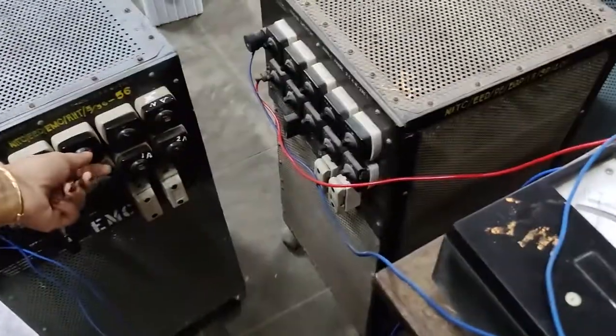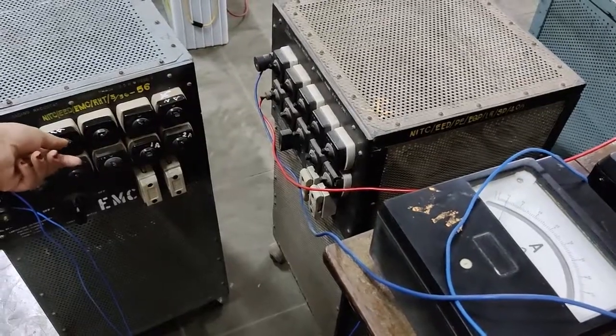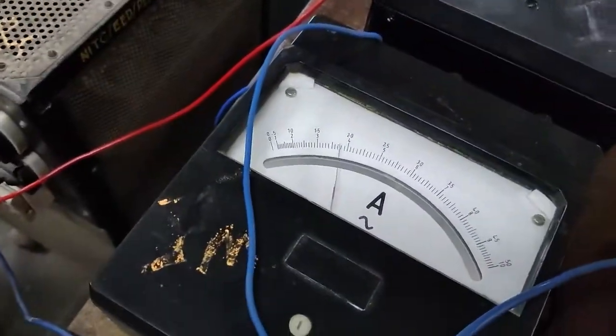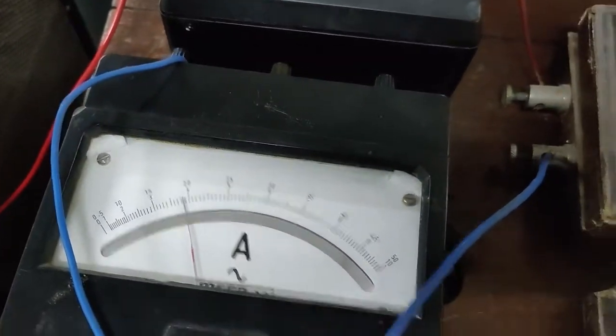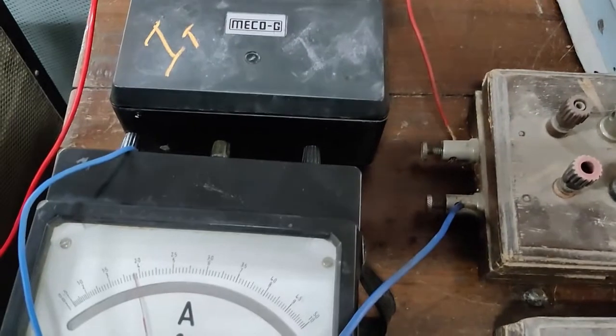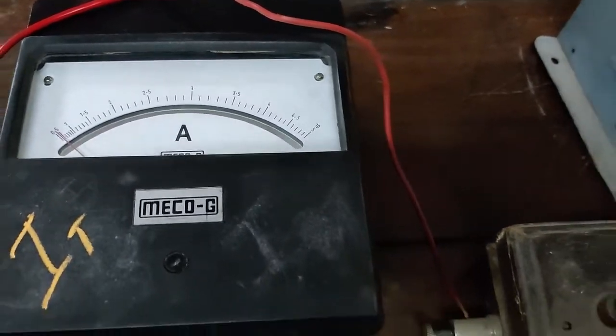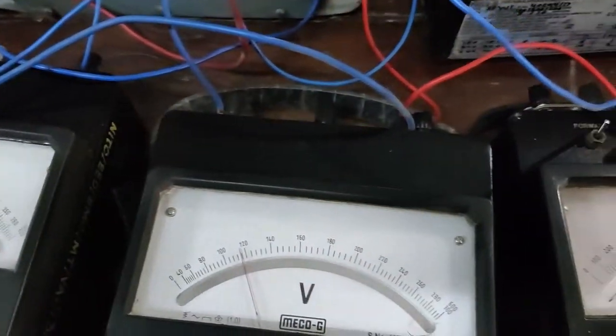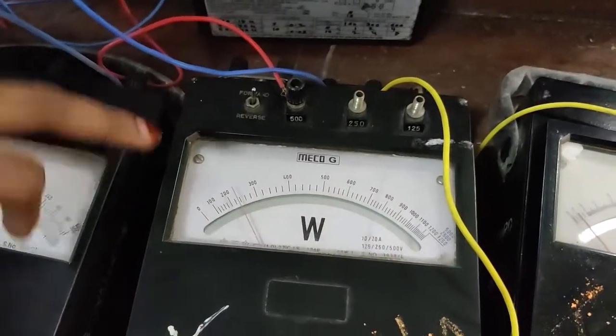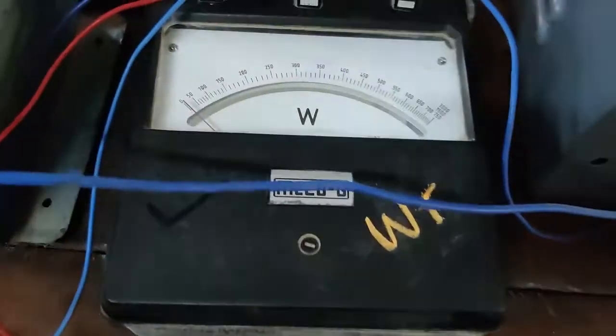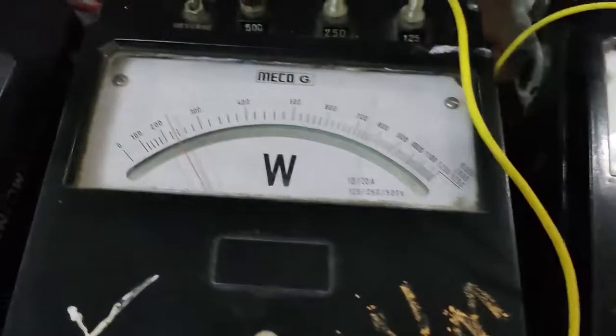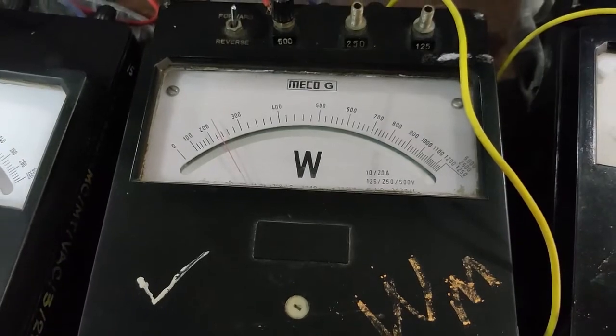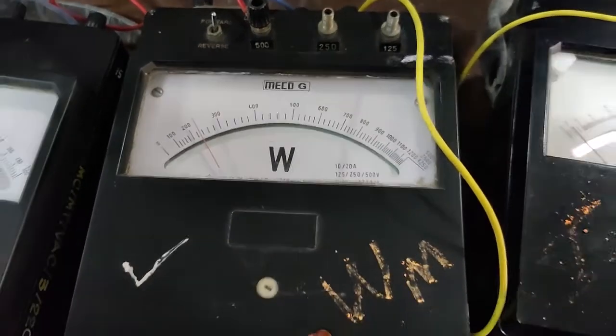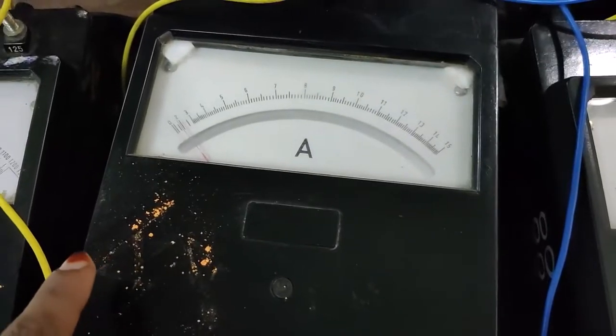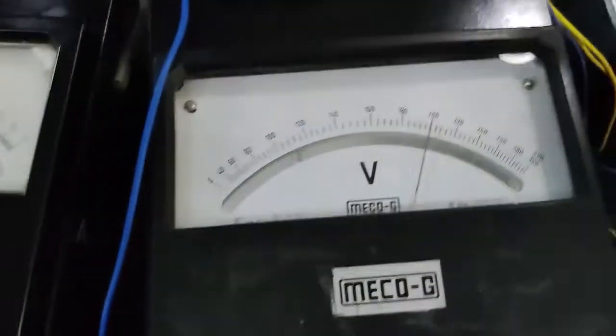Now we are turning on one more loading switch. Okay. Now the main transformer secondary current is increasing, and for this case also we want to measure all the meter readings, wattmeter readings WM, WT, and all the phase currents. WT increased. Okay, WM now you can see increased. WM is increased with the increase in loading. Current also increased.